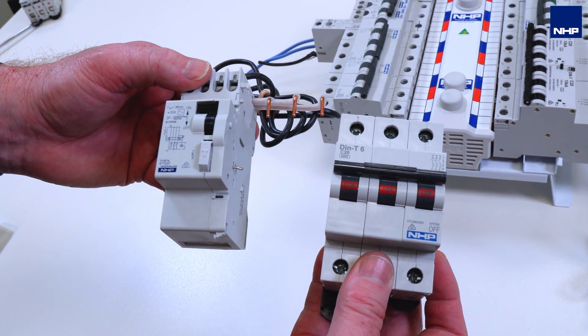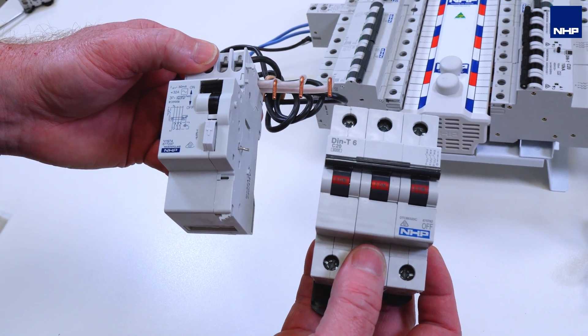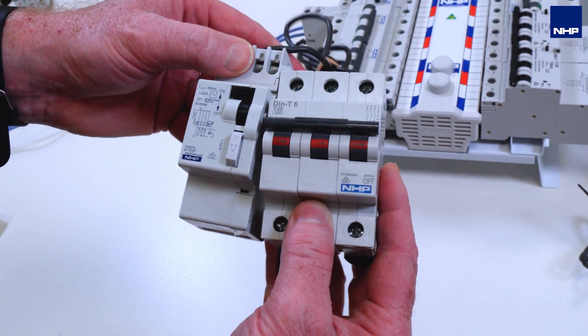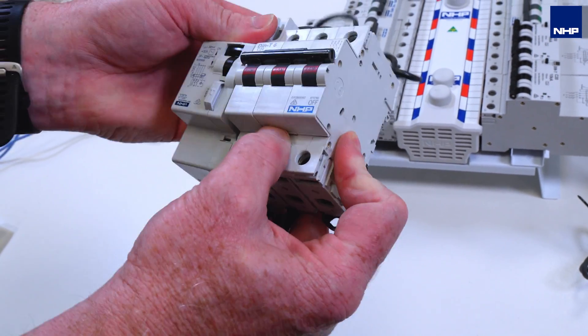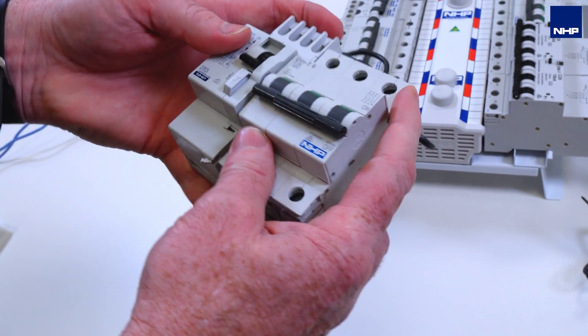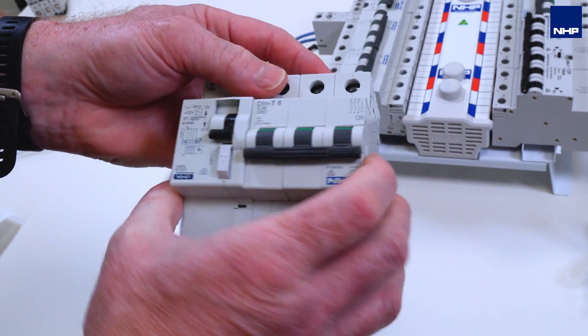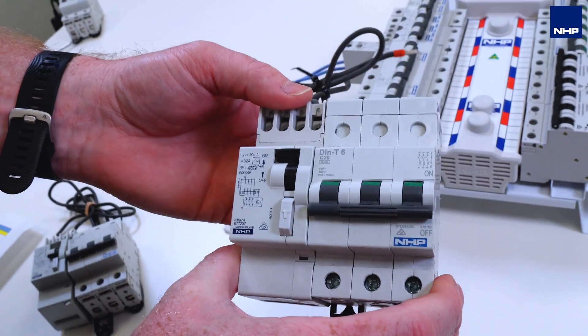The add-on modules are available from some companies in single pole width, two-pole width, or three-pole width. Here we can see the two-pole width. You attach it to the circuit breaker and it clips together. Both devices should be in the off position when clipping together. It snaps together and the end result is a product with all the terminal shrouds, as you can see here.